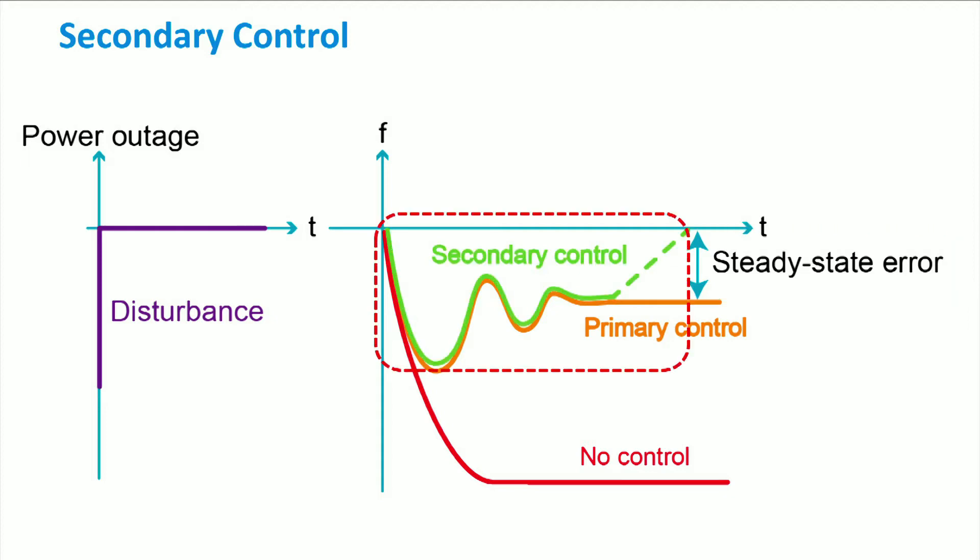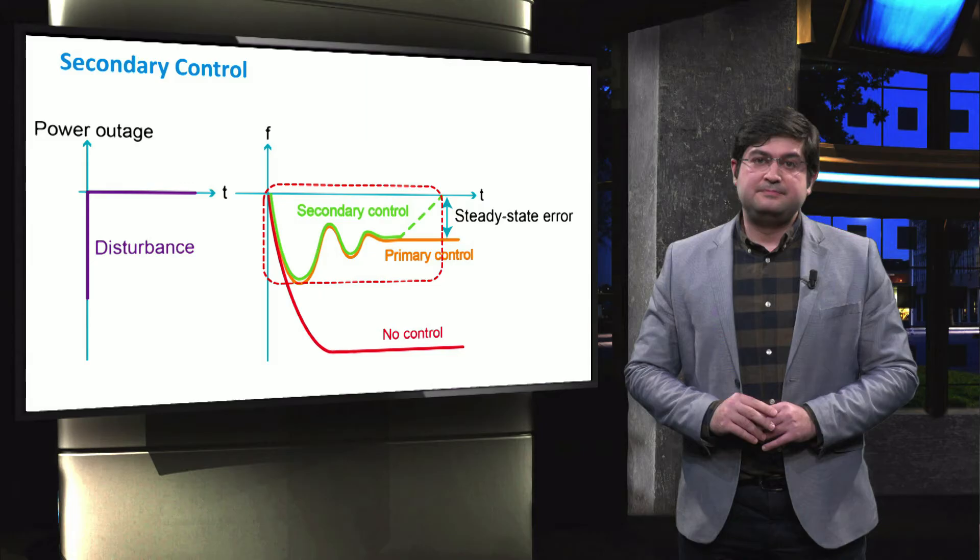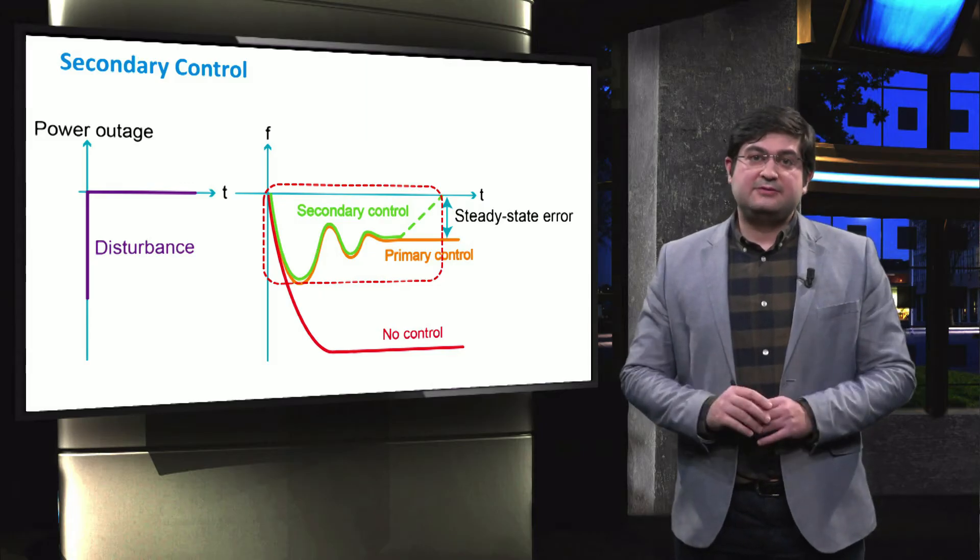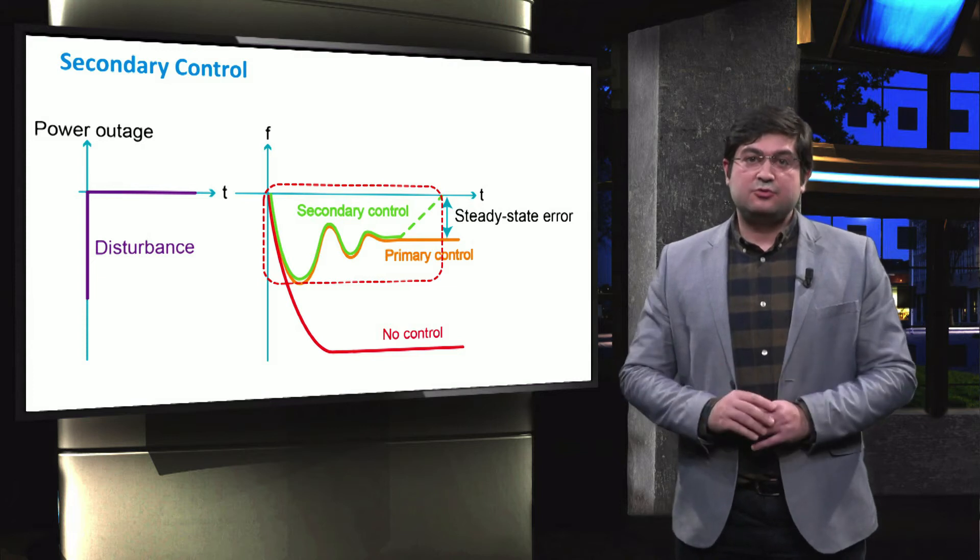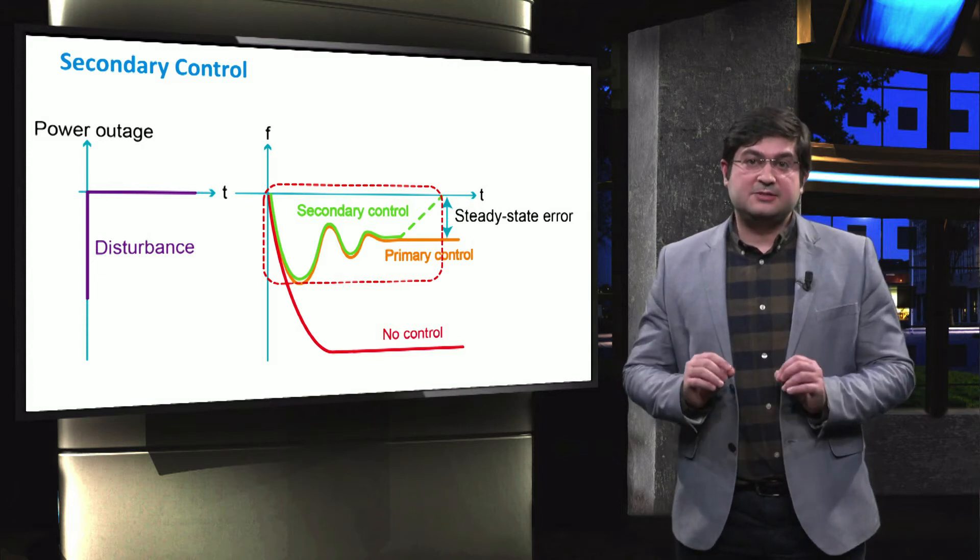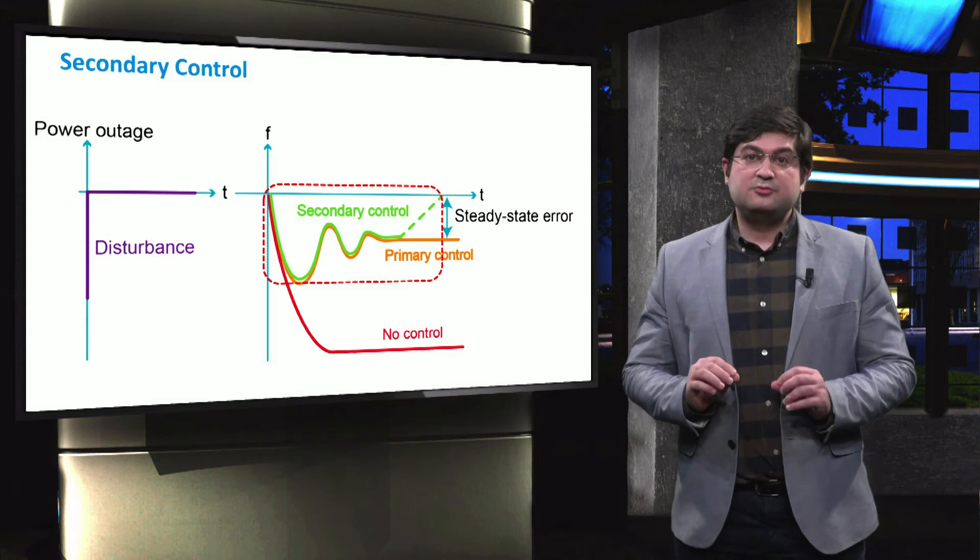To this end, the secondary frequency control, or the so-called load frequency control, is implemented that is activated after the primary control. It is an automatic control that restores the frequency back to its reference value in a centralized way, from one minute up to several minutes.